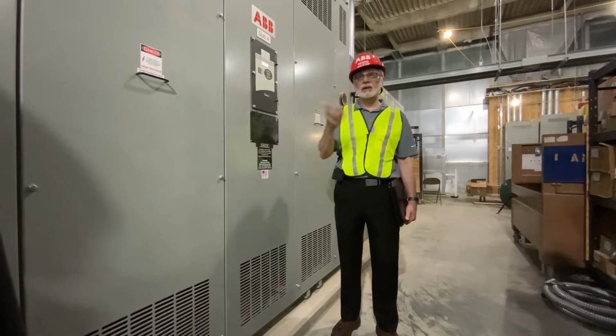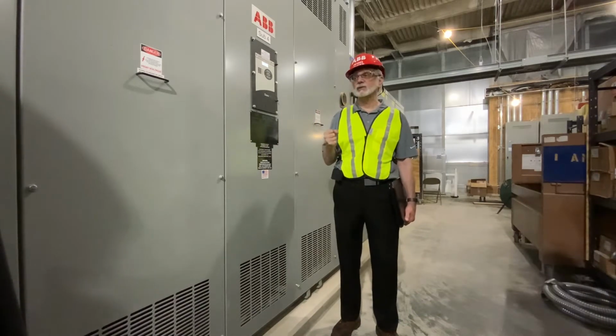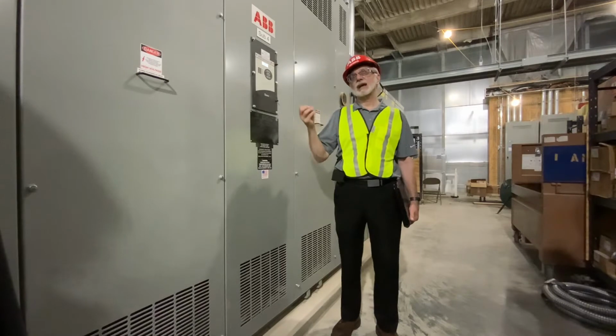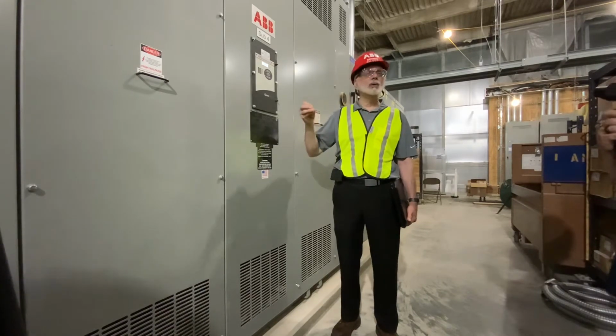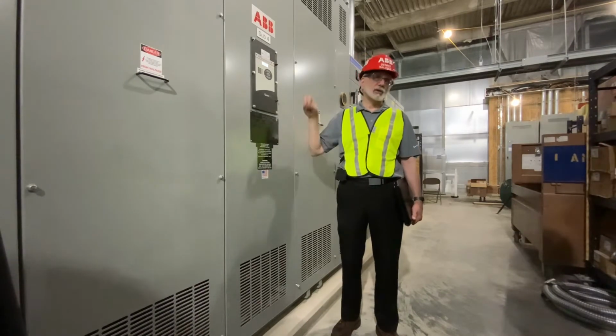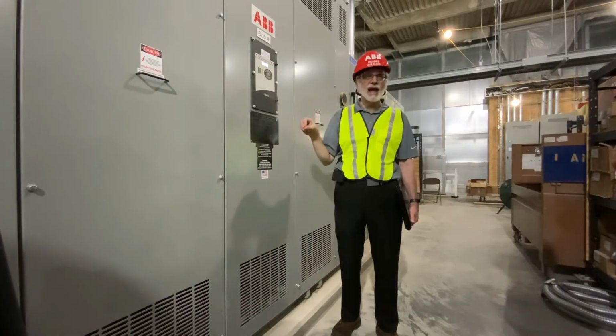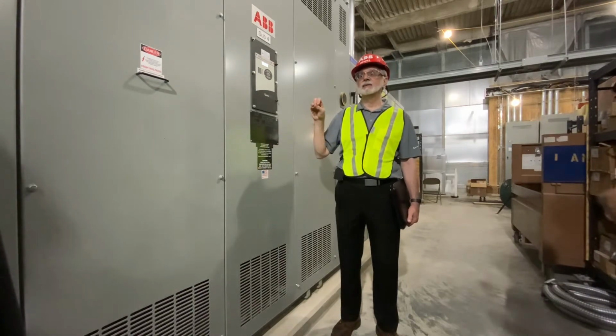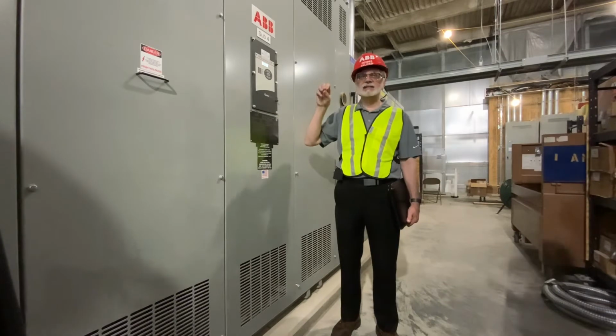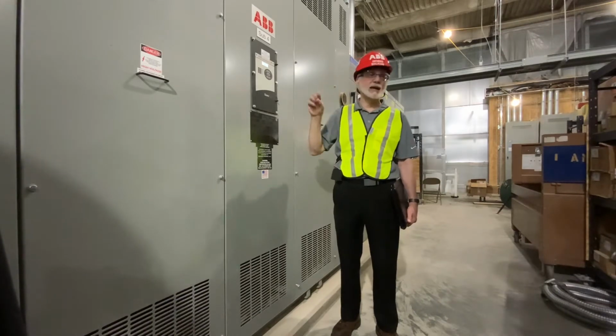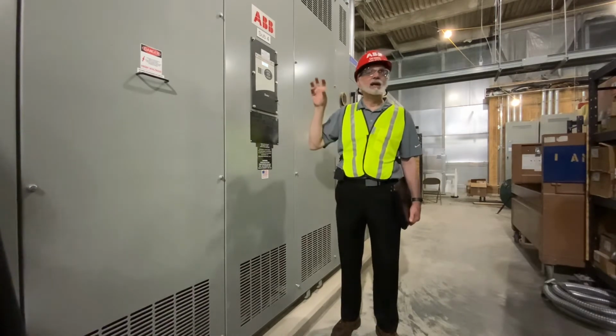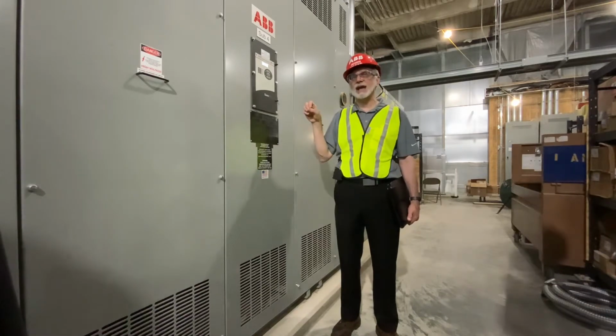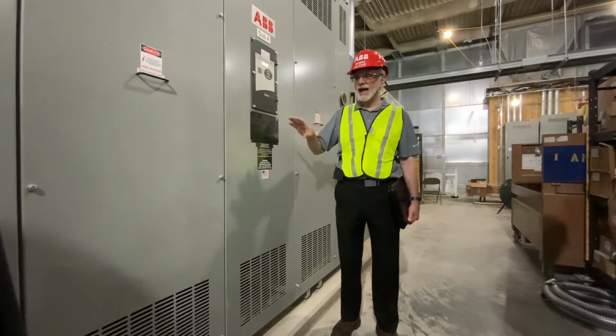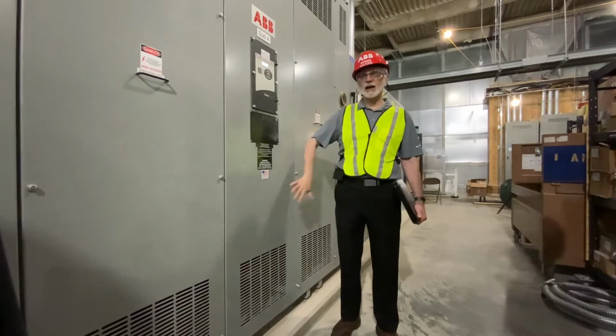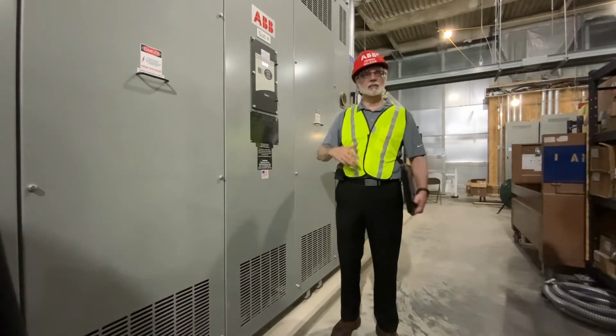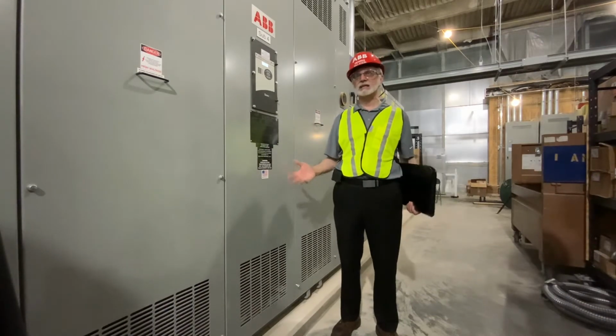And that will add to your transformer longevity, because what we don't want to do is start having corona issues or particulate matter doing some tracking in the transformers. Typically what happens is that's a death by 1,000 steps, okay? Once it starts to happen, it's very hard to make it stop. The other thing is transformers are warm, okay? One of their natural byproducts is heat.